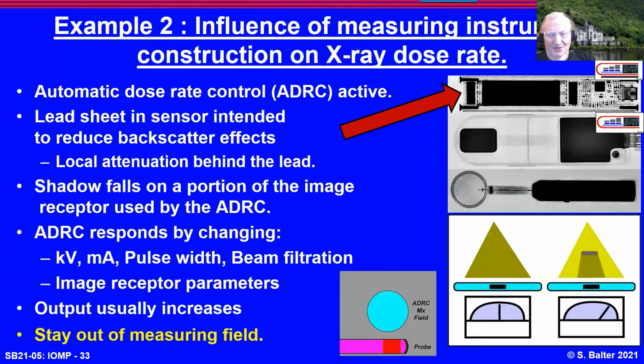This is a lead sheet that's put behind the sensor to avoid backscatter from the tabletop. Other instruments are more transparent. This is an example of a solid state detector. This is about a 50-year-old ion chamber with a very heavy metal stem. If you get in the beam, it will cause a shadow. If you're testing with automatic dose rate control, you will drive up the reading.